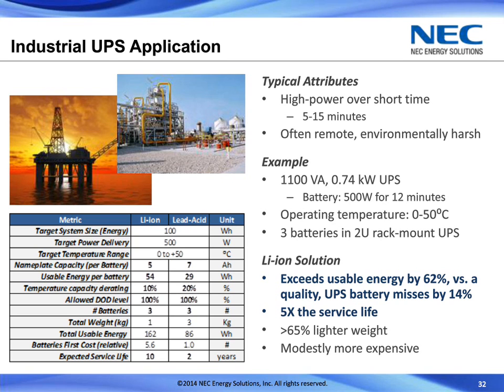You see a little bit bigger difference in the upfront cost, still about 5 times more expensive. But then again, you look at that service life, we're about 5 times longer there. So it does bring the cost down to the same area as the lead acid solution. So you can see the usable energy by 62%, whereas the lead falls short by 14, 65% lighter, which is pretty much always going to be the case, and like I said, a little bit more expensive for this particular application.